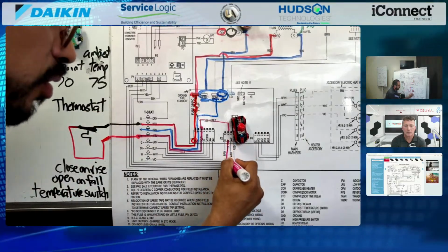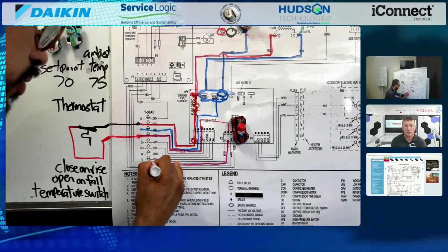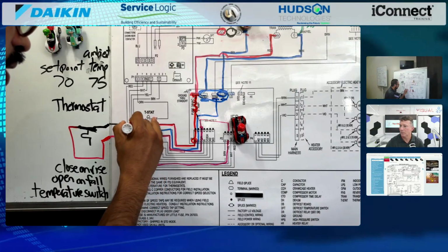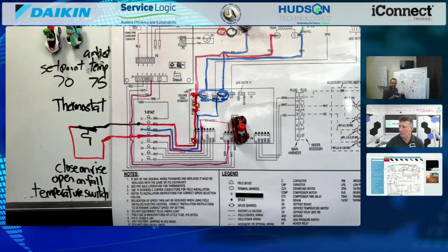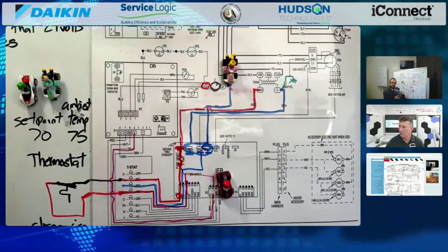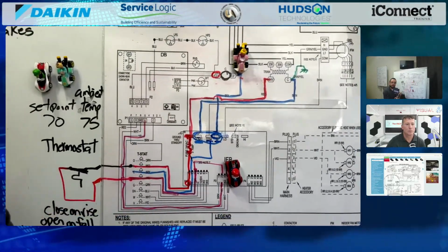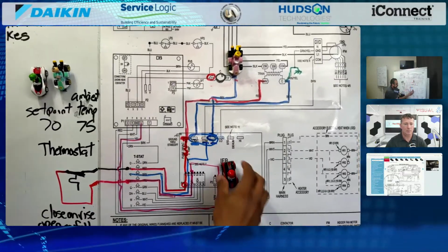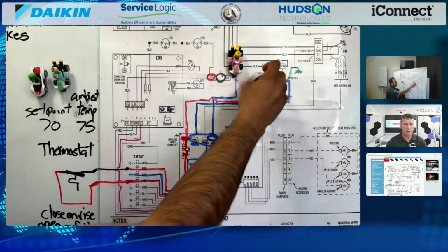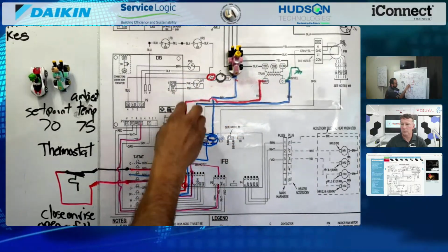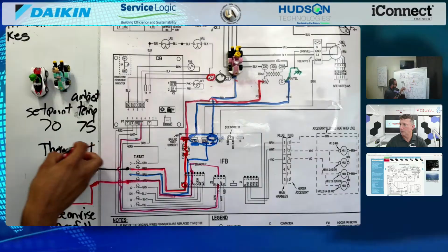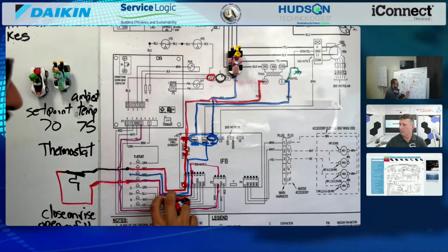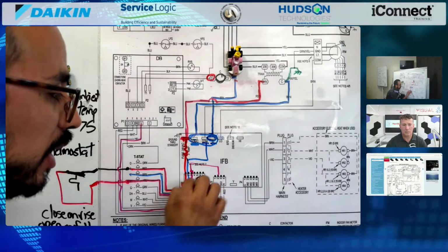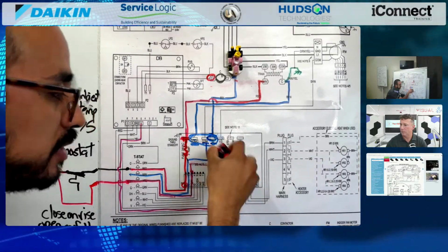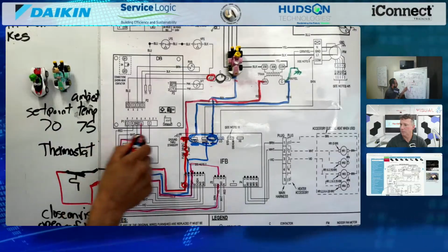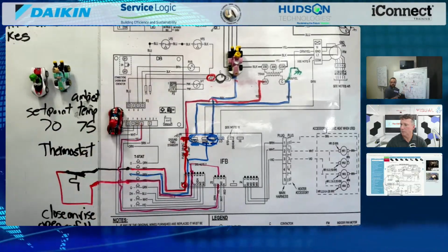Now, if you were to follow that yellow wire, let's follow it. Now, because this is a heat pump, there is a defrost board, but it's still a path that Mario takes. So here we go. Mario started here, he's going through the red wire on the board, through the fuse, going to my thermostat, coming back as Y, and then going through the Y on this little connector here. Internally, they're connected, and Mario continues the path all the way to the Y on the defrost board.